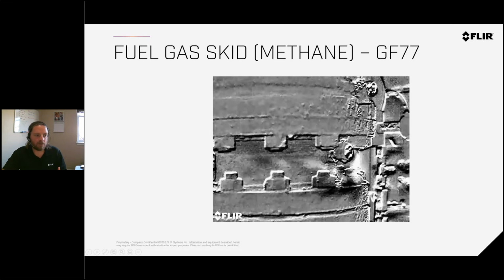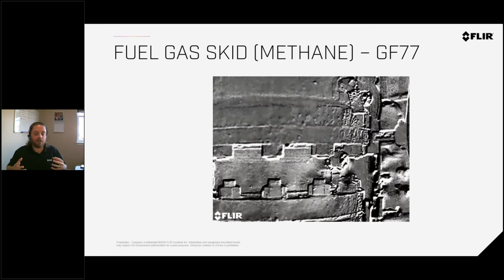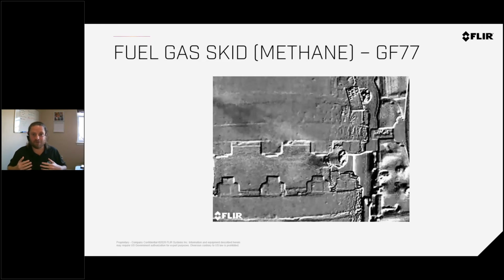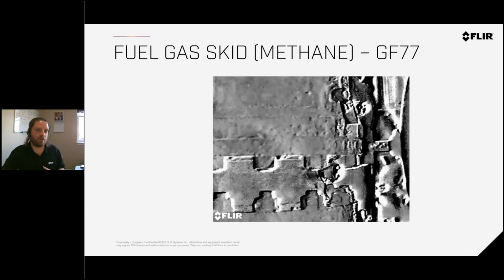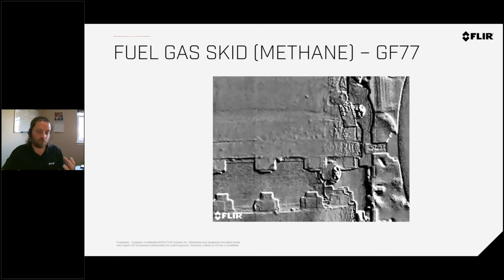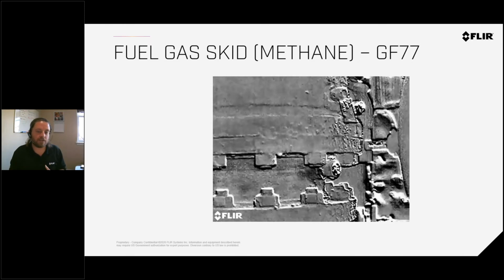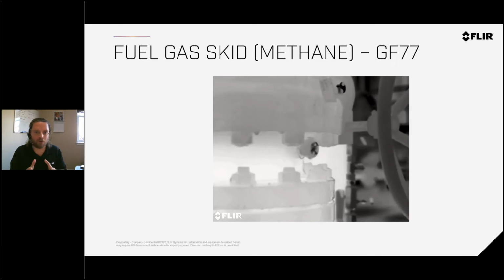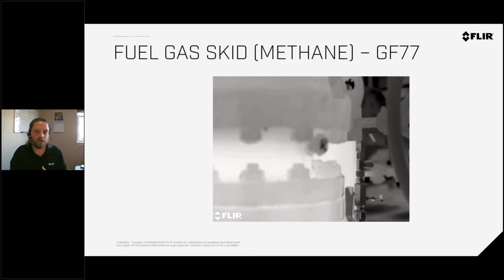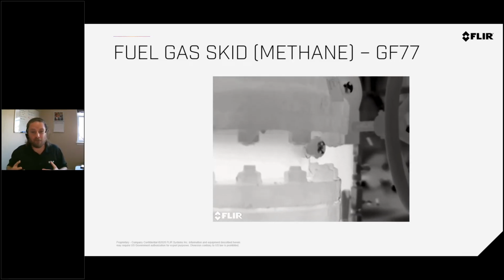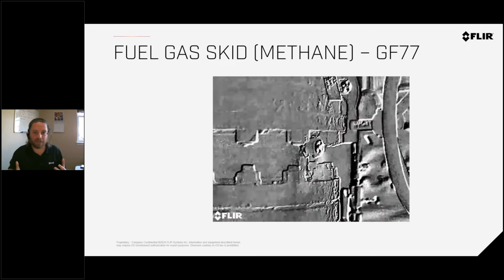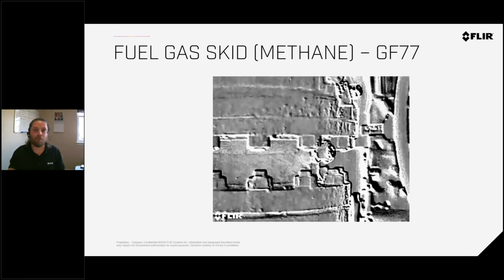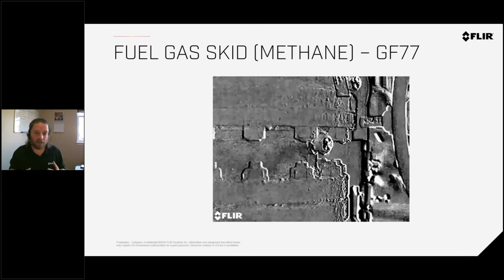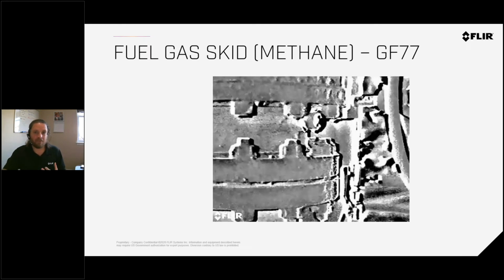This is a methane leak, and some folks say, well, hey, we put mercaptan in our methane to give it that smell. A very odorous smell that to our human nose is going to wake us up in the morning. We put mercaptan in there, so if there is a leak, we'll smell it and be aware of it. That works to a certain extent. But a lot of times, if you're working day in, day out in these plants and facilities, you might be used to that smell. You might become accustomed to it. Then when you go home at night and you have a natural gas oven and you smell that, that's a new smell for that environment. So it is a way to help warn us, but it's not always going to be effective. And that smell is still going to be in the air. You're not going to be able to smell it directly to a certain flange or valve easily by just following your nose.